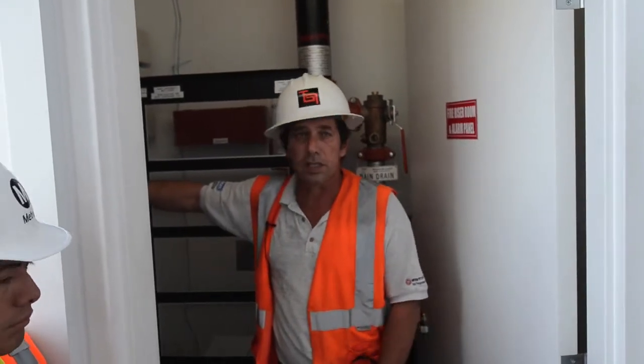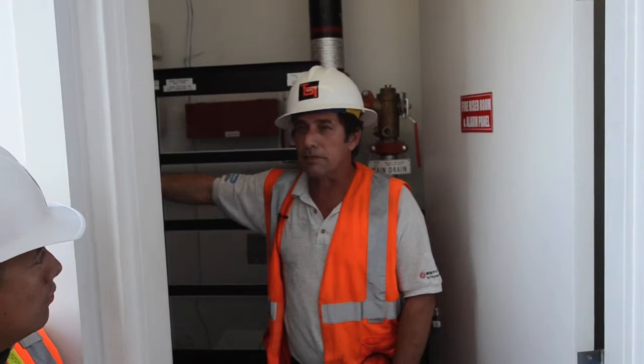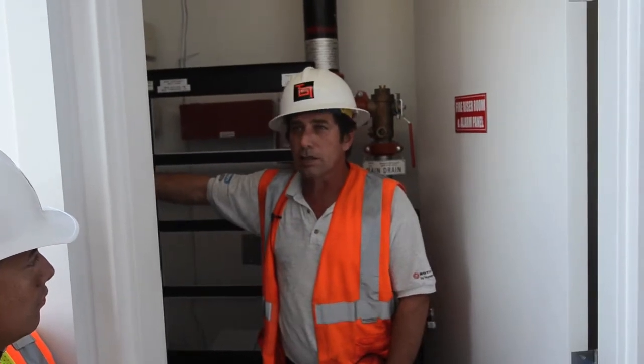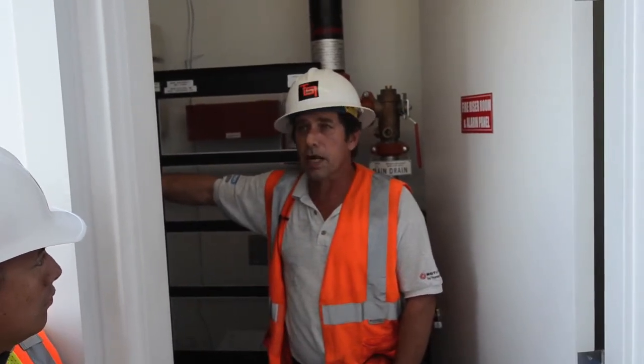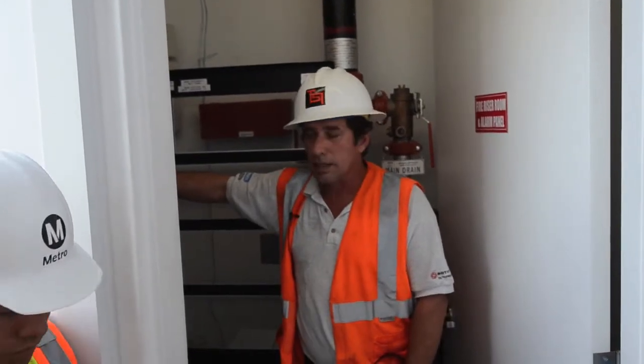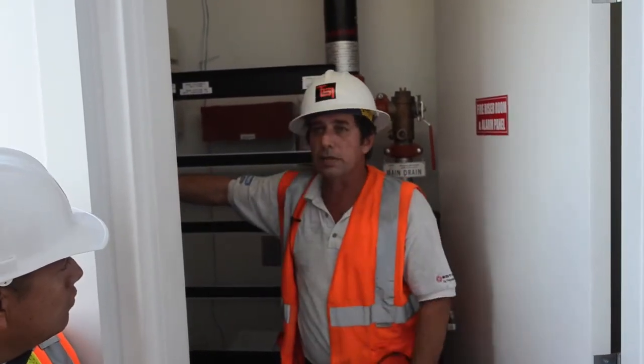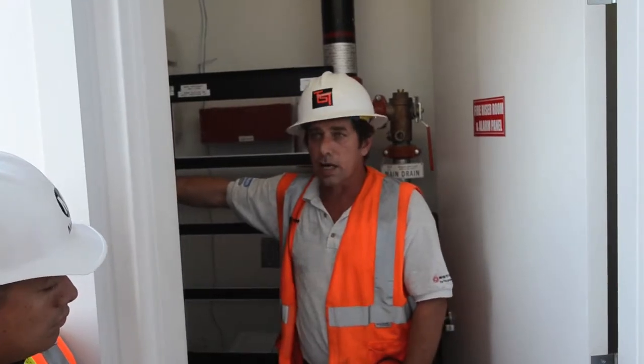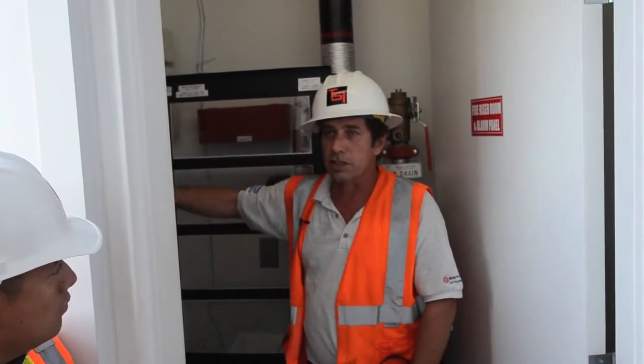per hour actually. Standard is, I believe, 4 air changes per hour. In the low-level alarm, we go to 6 air changes per hour. And in the high level, we go up to 8 air changes per hour. And that's an all-automatic function of the system.